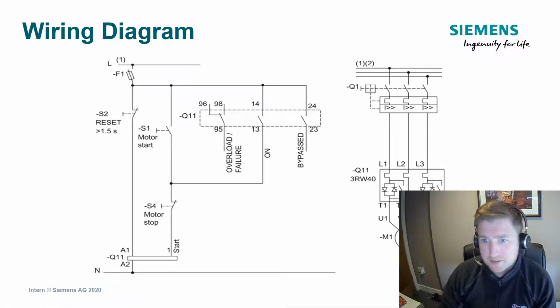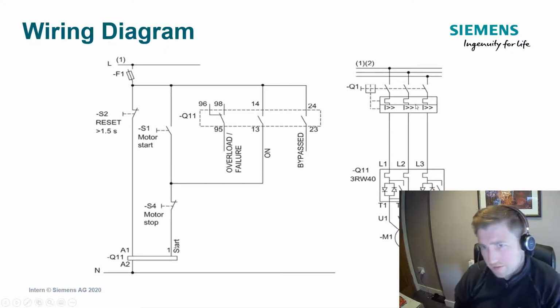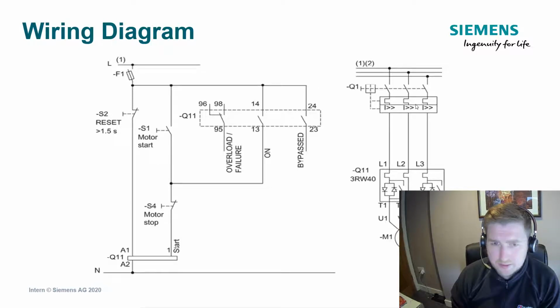So the idea is that now you've got an extra signaling contact here, and it works in a similar kind of fashion. Once you've removed A1 and A2, or the in signal from the soft starter, this mechanical bypass will then unlatch and the device will power down through these thyristors. So the way that the device would be configured would be you have the 3RW40 here in this main circuit. So the 3RW40 will take care of the starting of the motor, so in turn it has mechanical contacts in there that do the switching on and off of the motor, but you also have integrated evaluation for your overload protection of the motor, and you also have the thermistor evaluation if you wish to, dependent on the options that you select. Upstream of the device, it's always critical to have a form of short circuit protection. That can range from fuses to circuit breakers, dependent on what type of coordination that you're trying to achieve.